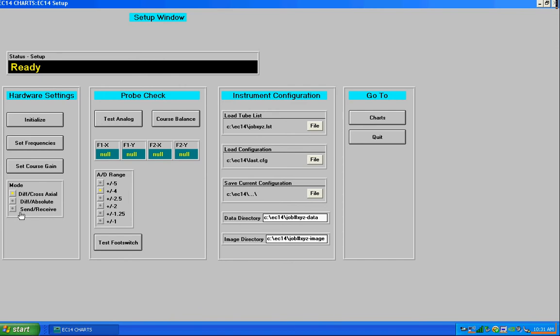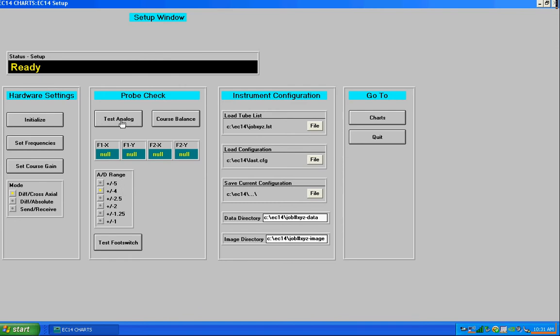This next section of the window is there to test the probe and also to test the foot switch. It also allows you to change the A to D range. So I'm going to go ahead and click on test analog. That's going to give me the individual analog values of each channel in the probe.